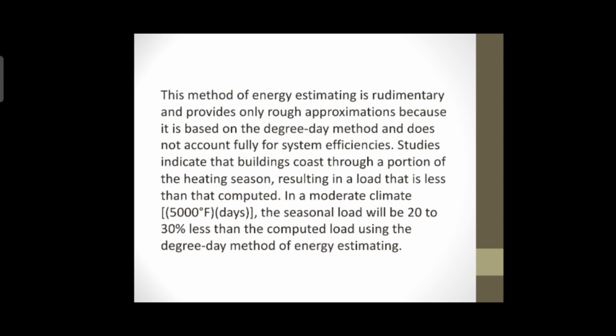On the other hand, additional system losses have the effect of increasing the load because some of the energy consumed is waste heat. These efficiency losses can be significant, particularly when the additional part load efficiency losses are considered. These factors are opposite in effect and have the outcome of roughly canceling one another, which results in an estimate that more closely represents actual performance.